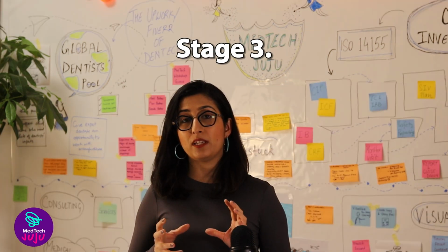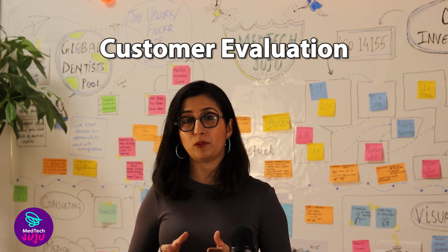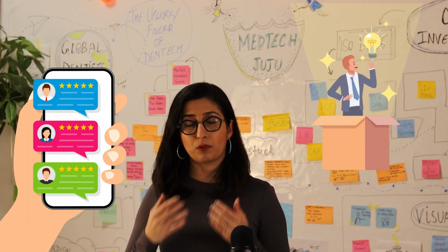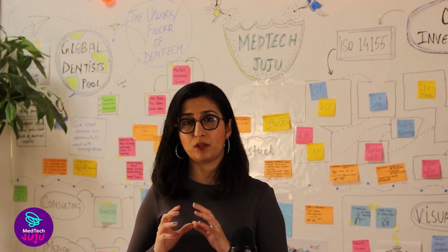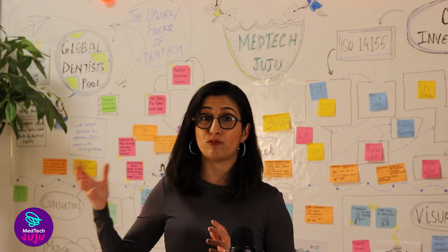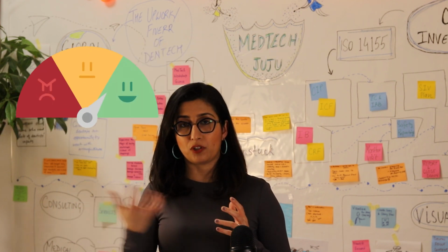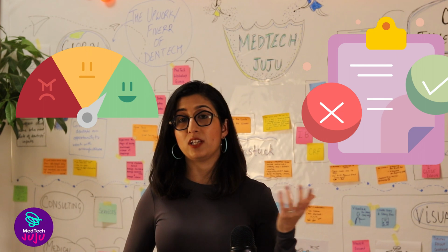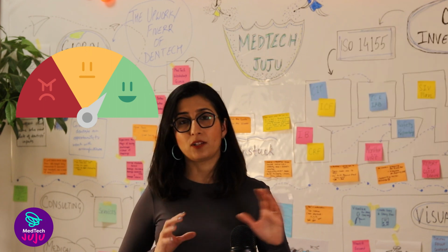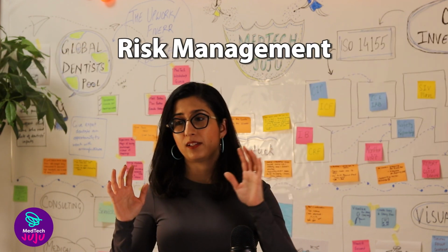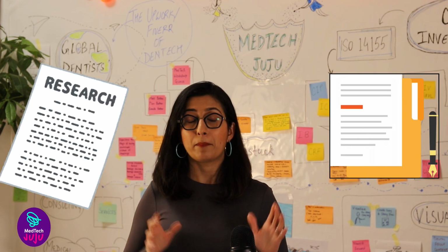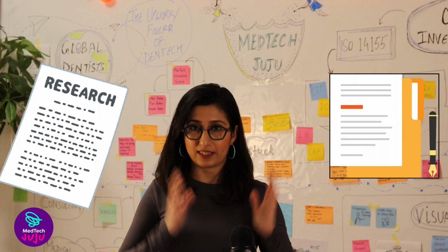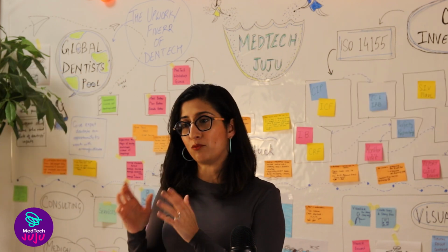Again, at stage 3, you're continuing with your customer evaluation, because you always want to show your prototype to as many clinical practitioners as possible so that you get as much input before you reach something called a design freeze stage. You also need to track how you're converting your customer feedback into actual engineering requirements. All of that goes into your risk management process, your design history file. Everything is being documented.